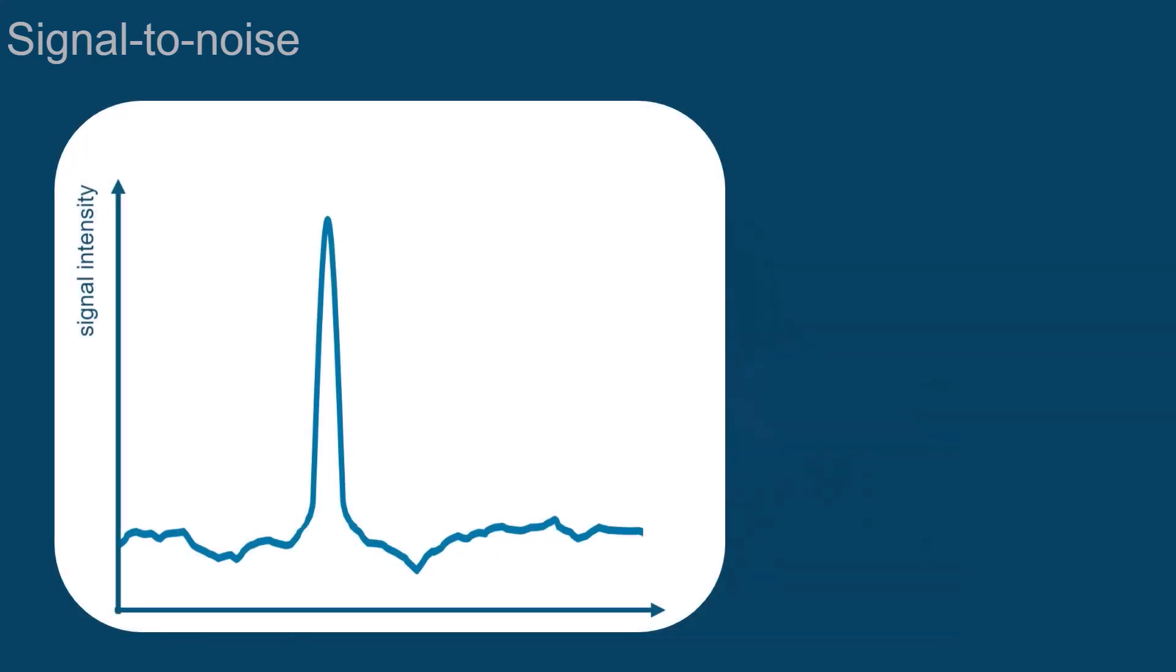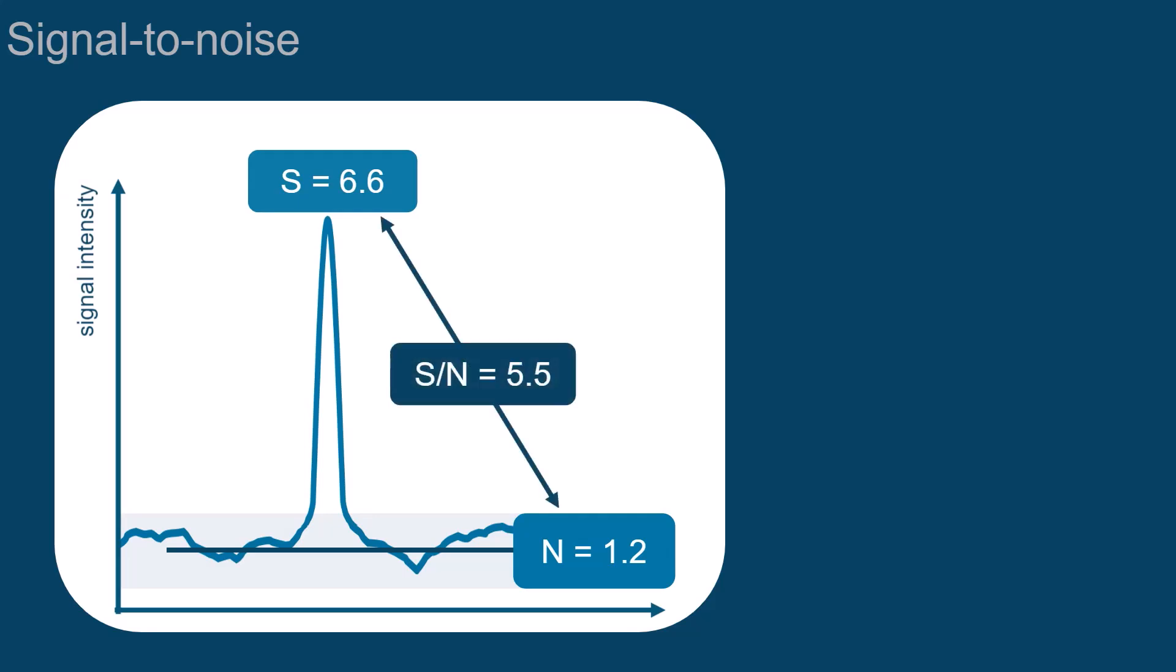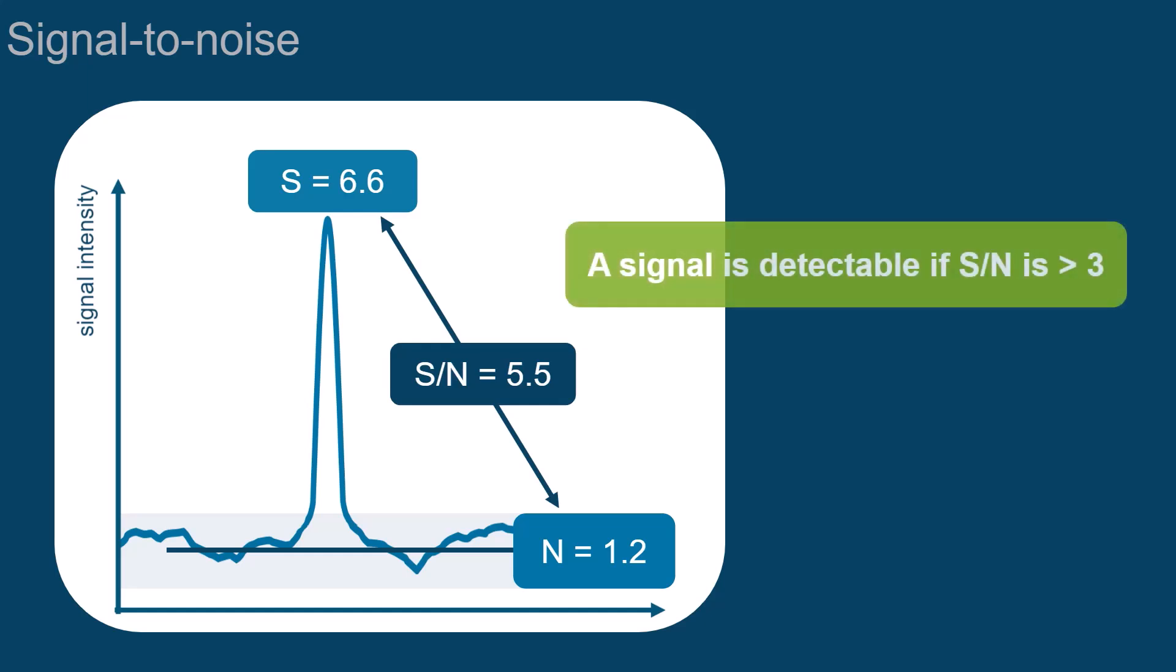To determine the signal-to-noise ratio, you need to read the intensity of the signal and that of the noise level, and then calculate the ratio of the two values. The signal is generally considered detectable when the signal-to-noise ratio exceeds the value three.